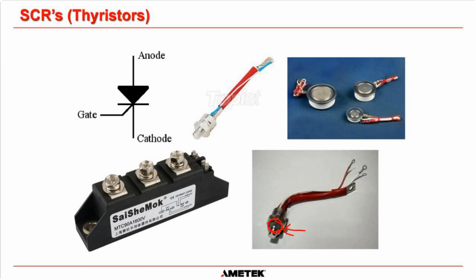On these surfaces on the hockey puck SCR, yes, this must have copper grease on it, because it gives a uniform connection between the device and the heatsink. Once again, on this portion here, you need to use copper grease.